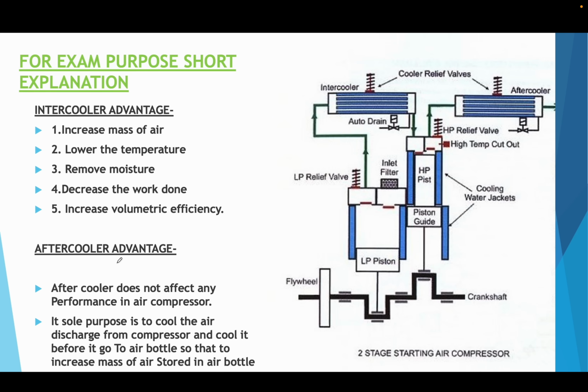If they ask what is the aftercooler advantage, first you say the aftercooler doesn't have any performance effect on air compression. Second, you say its purpose is to remove moisture content of the air, so that the mass of air stored in the air bottle should be more available for the purpose for which it is intended to be used.